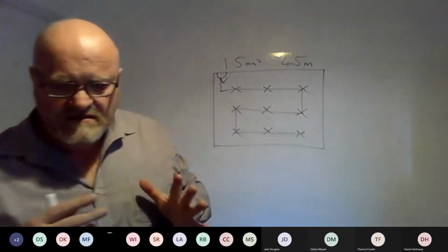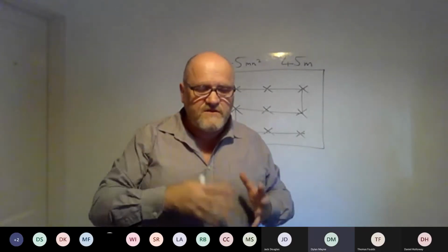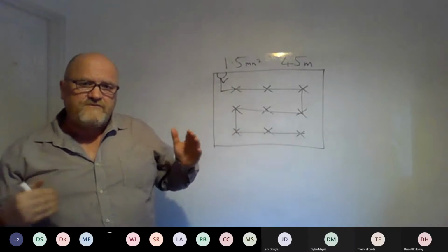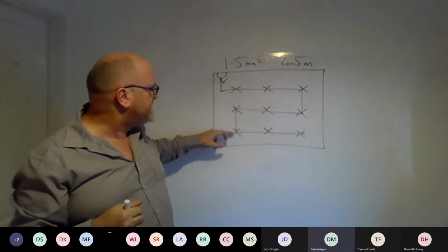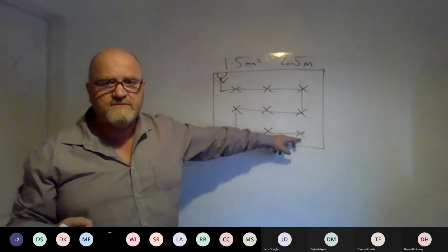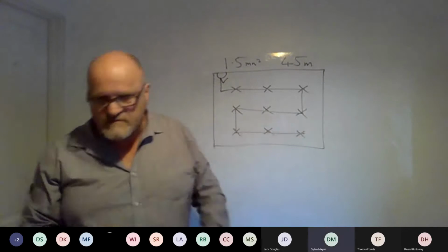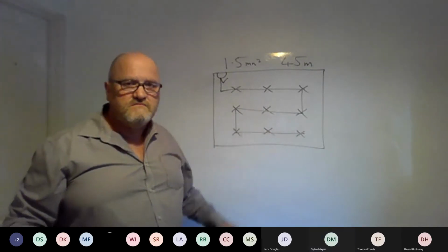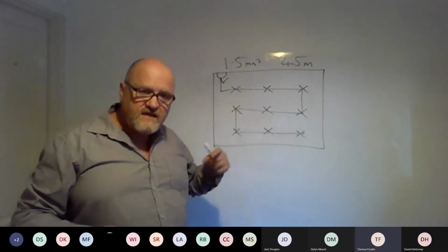But this resistivity, we use it for design. Once you know how to work out the resistance of a length of cable, you can work out what your expected readings are before you even build anything. And you need to know that. Why do you need to know that? Know how much to buy, but also when you're installing it, you know how much cable to work with.